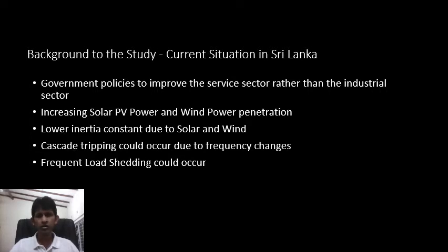Solar and wind power penetration also. For example, when you are talking about wind, we generate it by a variable frequency generator. Then we convert it into DC and then DC is being converted into AC again. So there is a double conversion and therefore mechanical coupling of inertia is not there. Similarly in solar, we don't have rotational masses. Because of this, the system inertia reduces drastically. And if a problem occurs in the system at this point, there would be more cascade trippings.